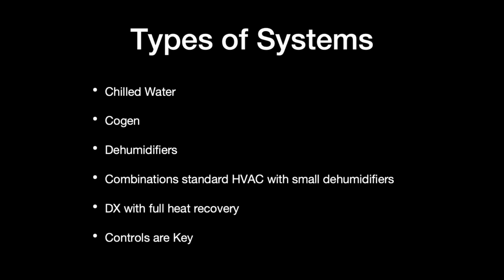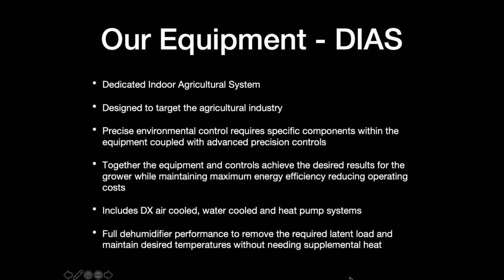The Cultiva Systems approach is DX with full heat recovery, and I'll get a little more into that as we go. But the controls are the absolute key to these systems. As I mentioned earlier, the flat temperature and humidity control is critical, particularly in the veg and in the flower stage. The equipment that we provide, we refer to as dedicated indoor ag system, or DIAS. We're differentiating that from a DOAS, or a dedicated outdoor air system. It's designed specifically for the ag industry.